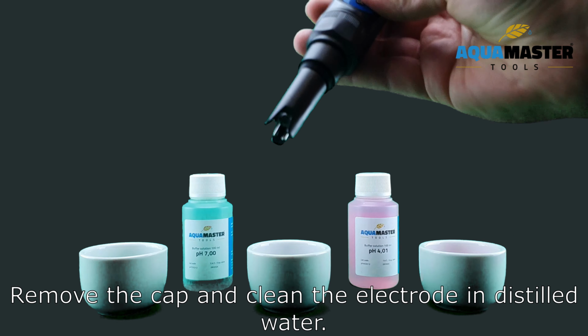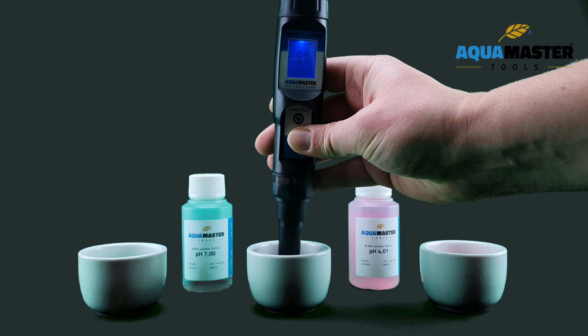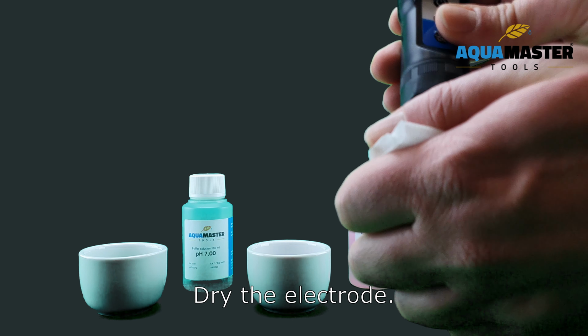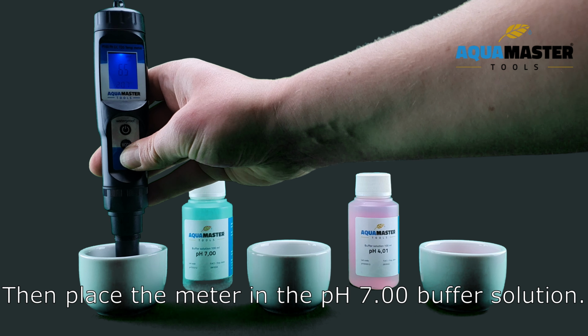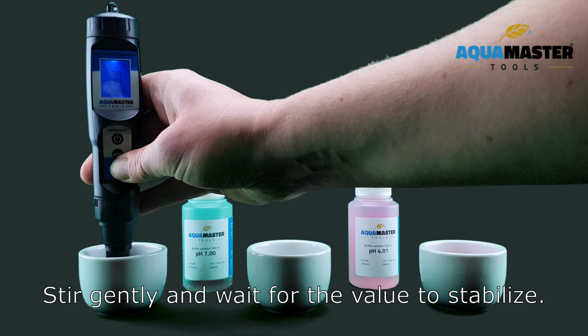Remove the cap and clean the electrode in distilled water. Dry the electrode. Then place the meter in the pH 7.00 buffer solution. Stir gently and wait for the value to stabilize.